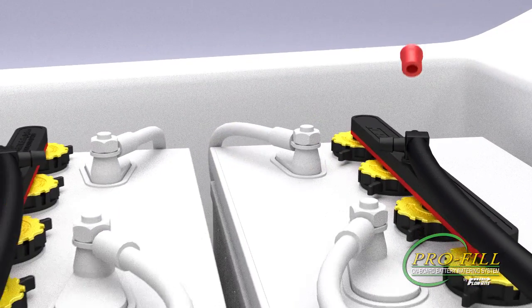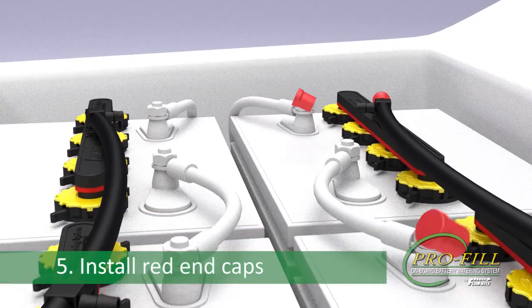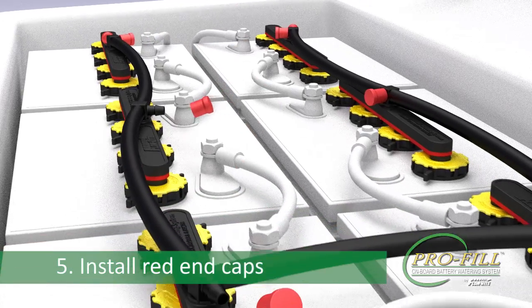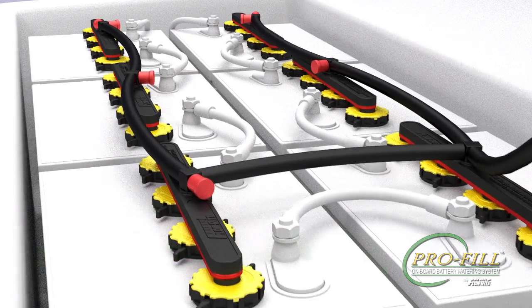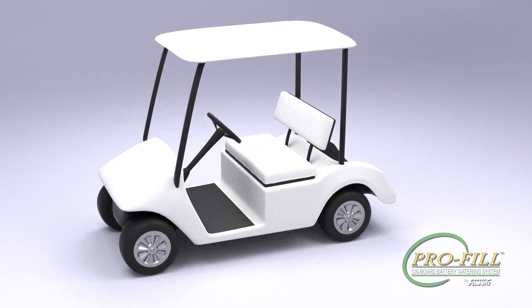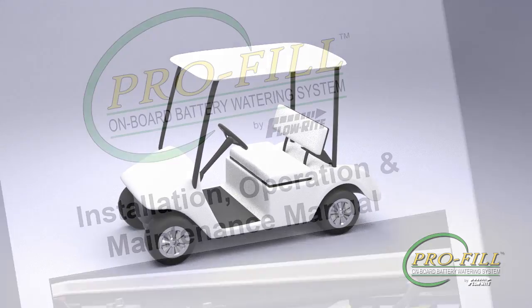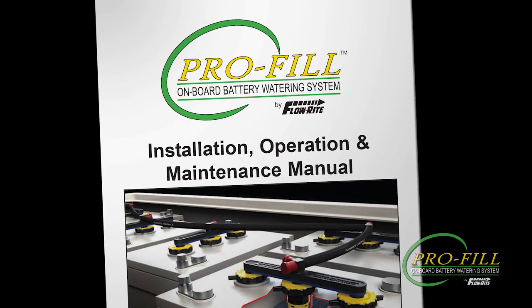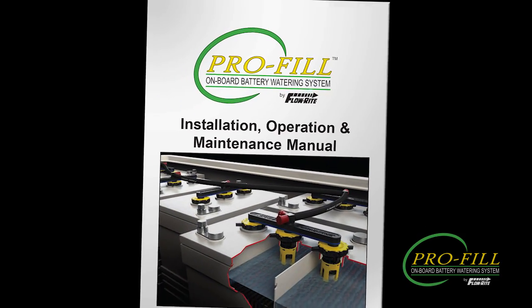Step 5: Complete the installation by placing red end caps on the remaining open ports. If you are installing a Pro-Fill system on brand new batteries, be sure to wait at least four charge cycles before adding any water.